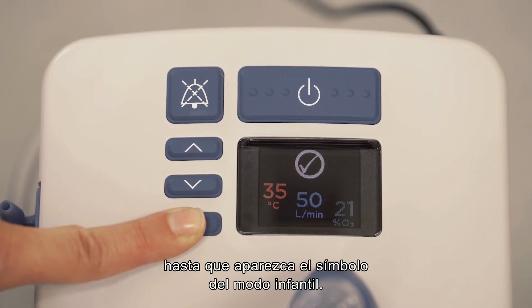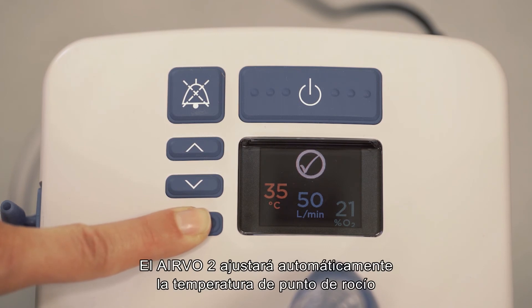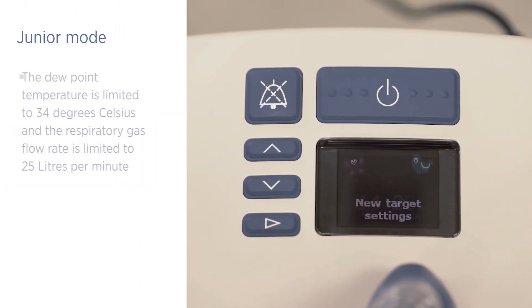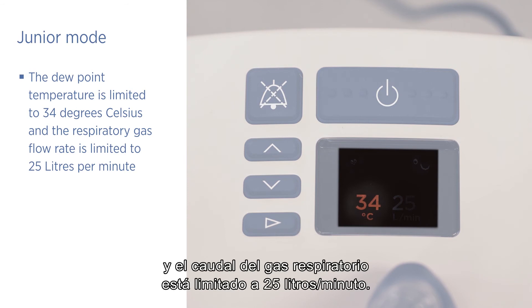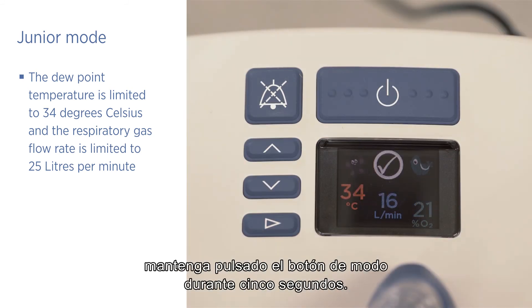If the patient will be using an OptiFlow junior nasal cannula, you must activate junior mode. Press and hold the mode button for five seconds until the junior mode symbol appears. The AIRVO 2 will automatically adjust the dew point temperature and gas flow to safe limits for the junior interface. The dew point temperature is limited to 34 degrees Celsius and the respiratory gas flow rate is limited to 25 litres per minute. To deactivate junior mode, follow the same procedure — hold the mode button for five seconds.